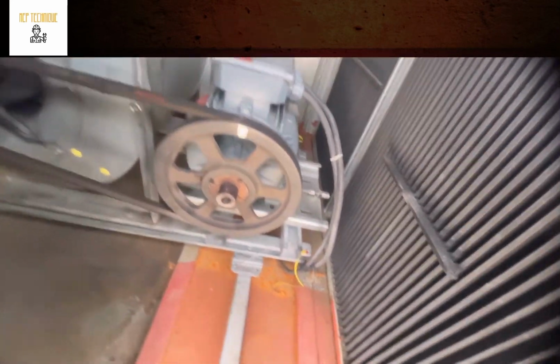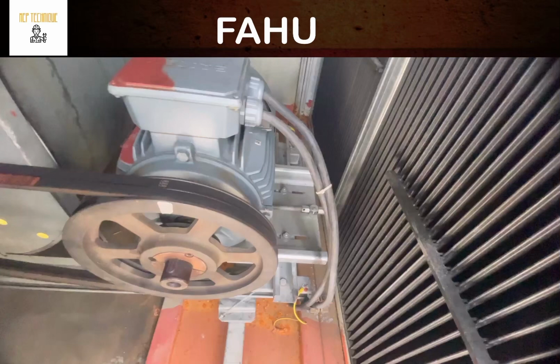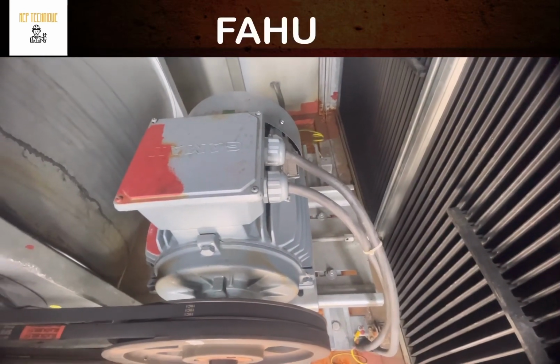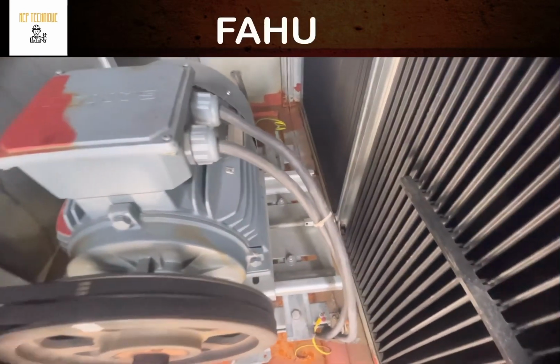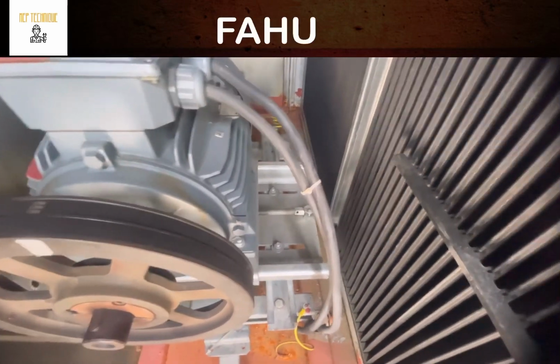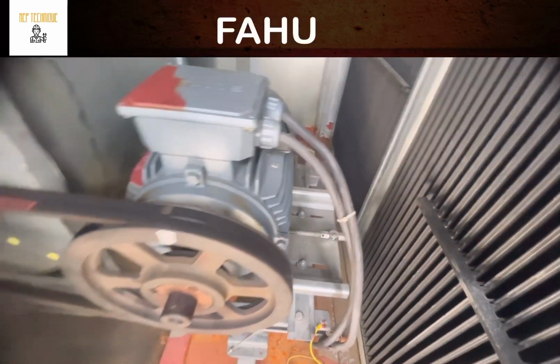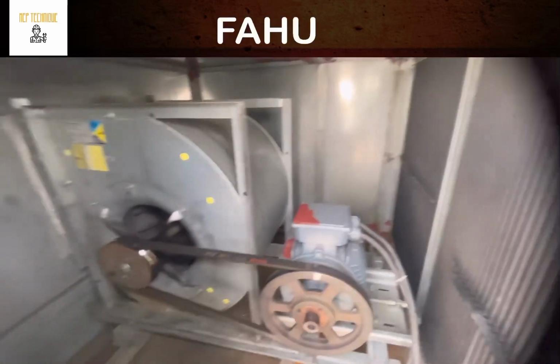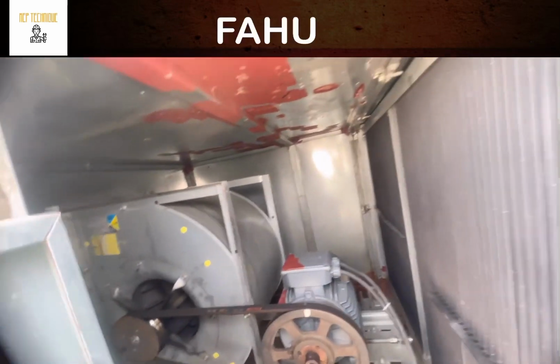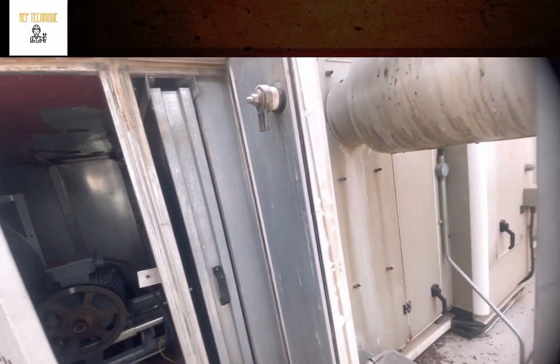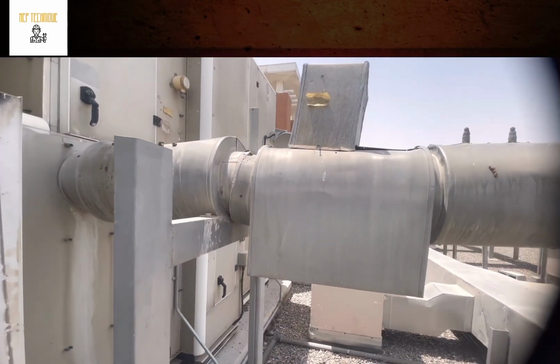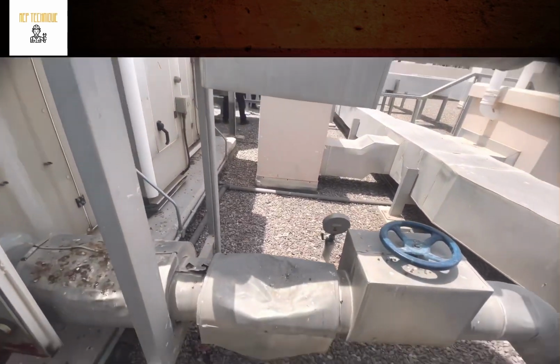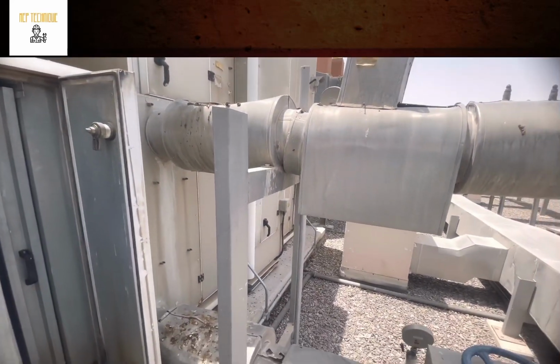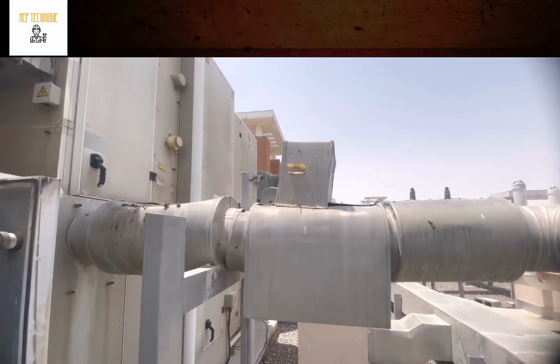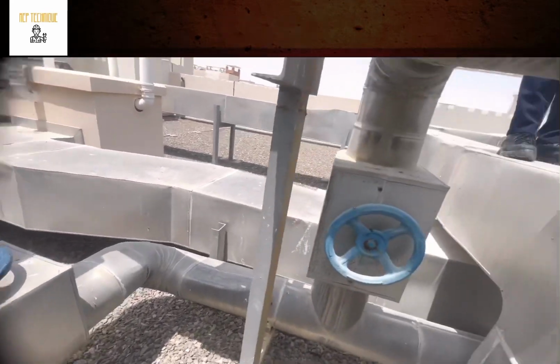Also the motor. This is the mechanism to adjust the belt tension. You can adjust the belt tension here. Move the belt. Then after that we'll move to the chilled water section. After the chilled water system, we'll discuss the air controlling system. There are two chilled water lines. This one is chilled water in, and the chilled water should always come in from the downside. This is the return line. In the chilled water in, you can see there is a bypass valve.